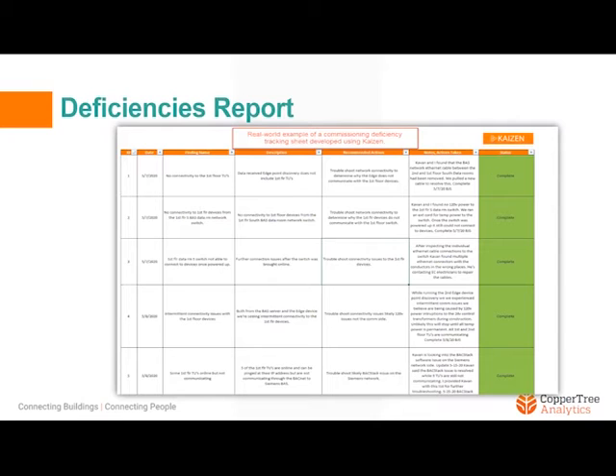If you follow the workflow for the top row, you can see that the finding was related to a connectivity issue to the first floor terminal units. The description and recommended actions provide additional details and instruction. In this case, it was determined that the network communication for the first floor devices needed to be further investigated, and it was then noted under actions taken that they found a BAS network Ethernet cable had been removed.